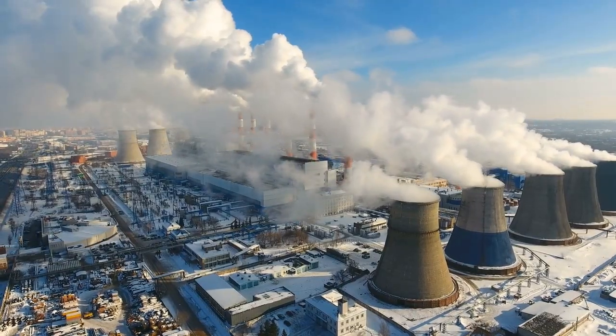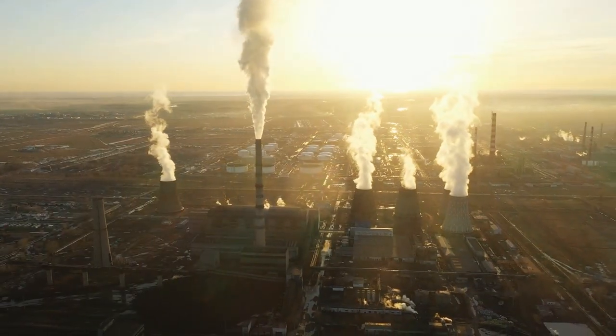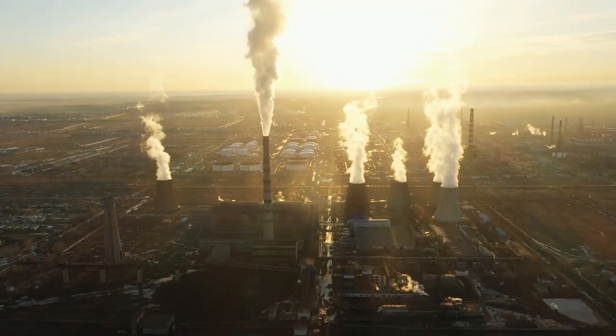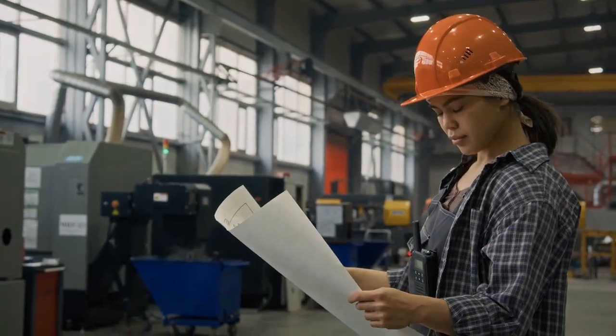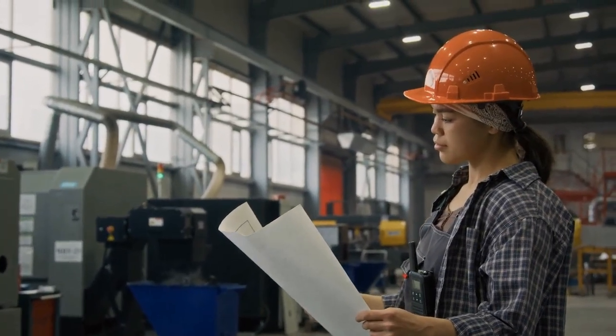Now then, if we look at process heat and steam, which is a large energy use in industrial sites, you're looking at combustion efficiency, condensate return for steam systems, heat recovery, good maintenance practices to prevent fouling. You also need to look at control strategies that interact well with the production scheduling and don't impair production. On refrigeration or process cooling, well, there's of course seasonal profiles to consider. There's part load efficiency issues and problems with equipment needing maintenance, like condensers needing to be maintained. And also then there's nuances around changing set points and the knock-on effects that can have.